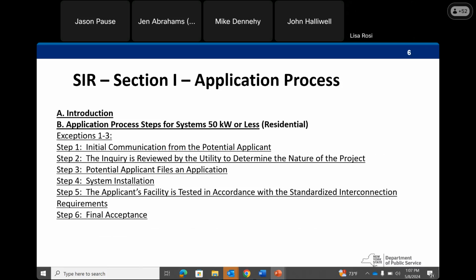I thought the best way to go over this was to look at the table of contents of the SIR and walk through it. Section 1 of the SIR is the application process. There's an introduction with background information on interconnections, and then Section B covers the application process for systems 50 kW or less—mostly the residential section for typical rooftop PV and other small DER/ESS interconnections. There are a couple of exceptions developed over the past years, outlined where utilities could apply for an exception for larger systems above 50 kW.